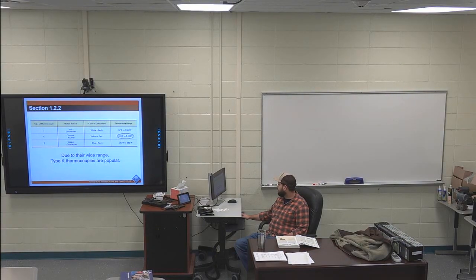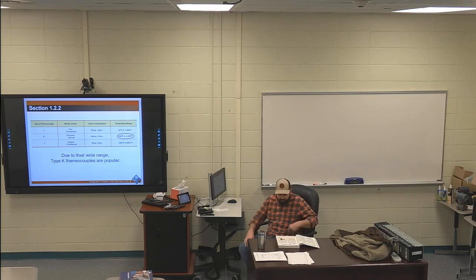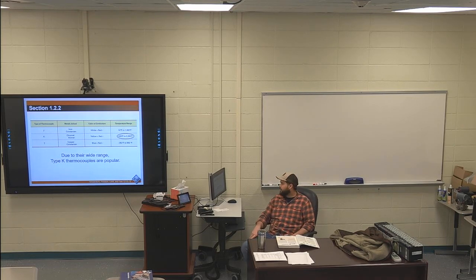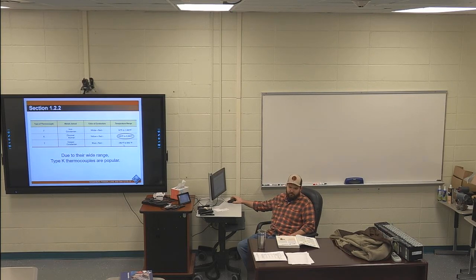There's your board. I think in Instrumentation 3, when we go through temperature stuff, they have a scale. This one doesn't have a scale in it, but there are certain thermocouples that have a range. If you see the temperature range of the 3 types, obviously you want to pick the one closest to the center of your range. You don't want to pick a thermocouple that's all the way on one side. If I was measuring temperatures up to 1300 degrees, I wouldn't pick a type J. I would pick a type K so that it's more in the middle.